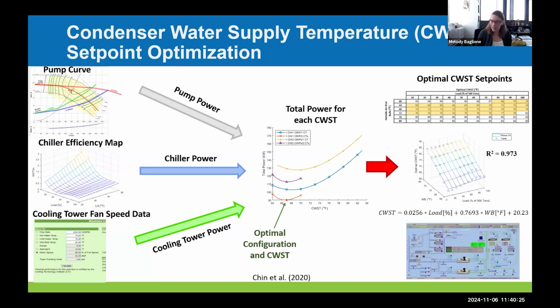And they plotted that over various loads for our 500-ton chiller and various wet bulb temperatures, and came up with a formula, because our building management system could only take a formula to set the condenser water set point. So they did a regression fit of the data from the optimization study and actually implemented that into the building management system so that it recommends optimal condenser water supply temperature.